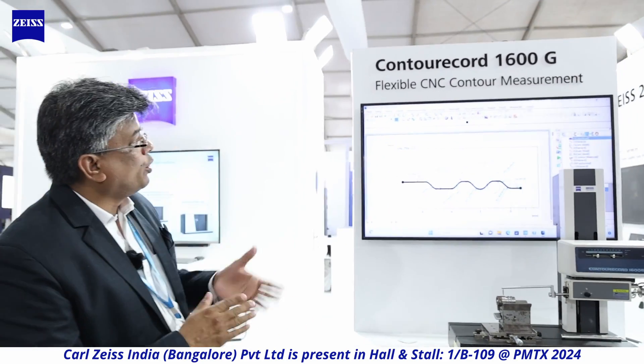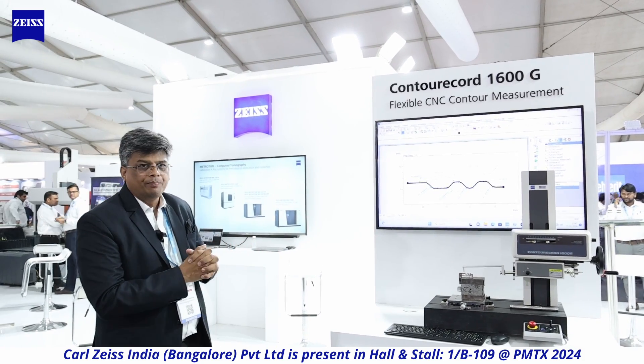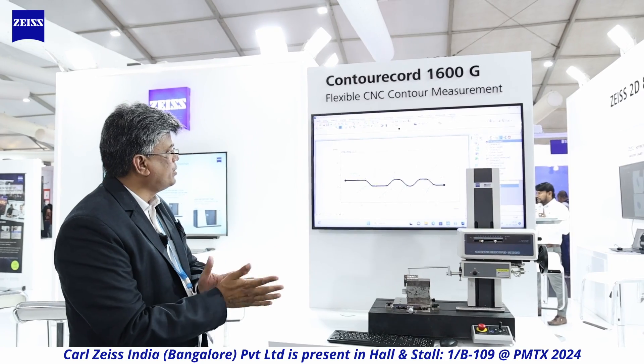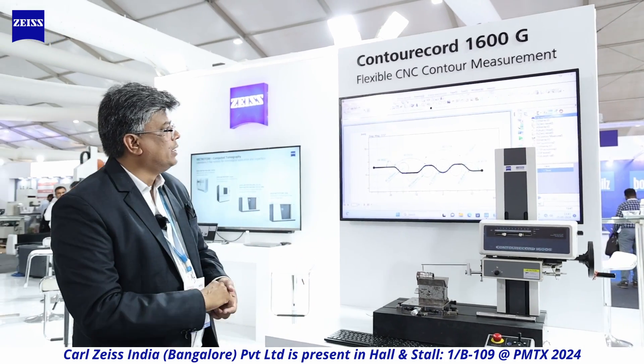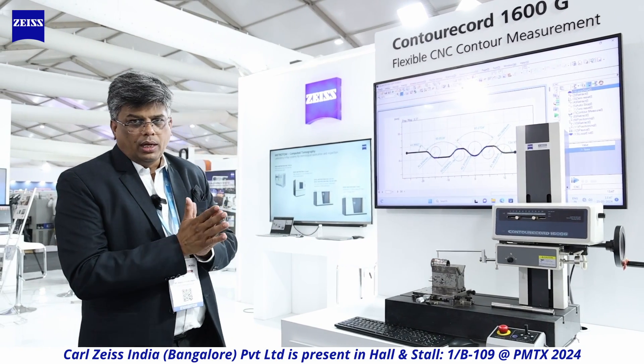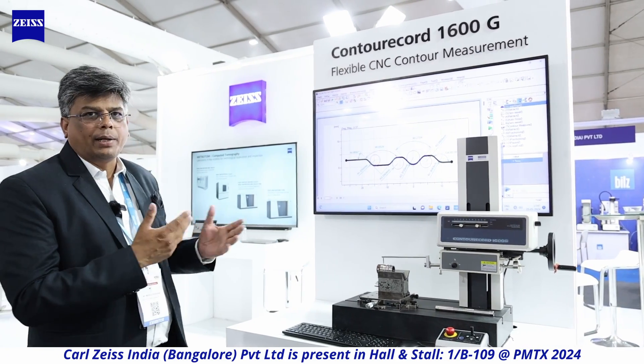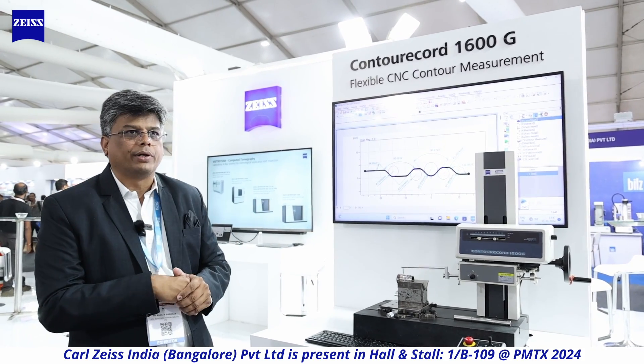Next is the Contourecord 1600 G, a flexible CNC contour measurement system. 2D contour measurement uses a sharp stylus of 25 microns, which runs on the tool to collect the profile as shown here. The profile can then be compared with the CAD model, or you can perform 2D dimensional analysis on top of it.